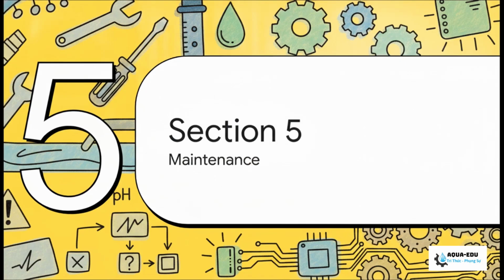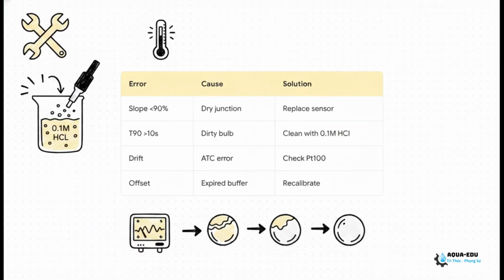All right, getting into Section 5, Maintenance and Troubleshooting. Keep this troubleshooting cheat sheet handy in your tool bag. If your slope suddenly drops below 90%, you probably have a dry reference junction. If your readings are drifting all over the place, check your ATC temperature sensor. But I want you to pay special attention to a sluggish T90 response time. If it takes forever to read, it usually just means the glass bulb is coated in scale or oil. You don't need to throw it out and buy a new sensor. You just need to gently bathe that glass bulb in a 0.1 molar hydrochloric acid solution to dissolve the scale. Just remember, be gentle and don't scrub it.